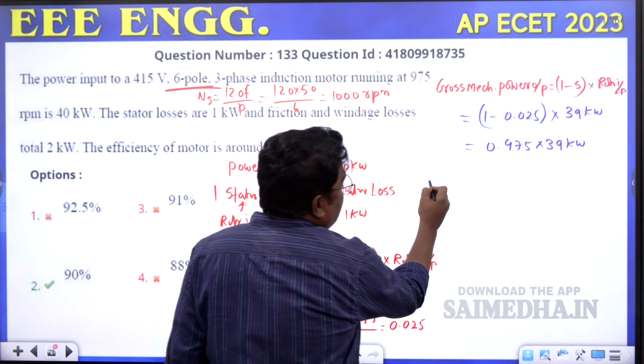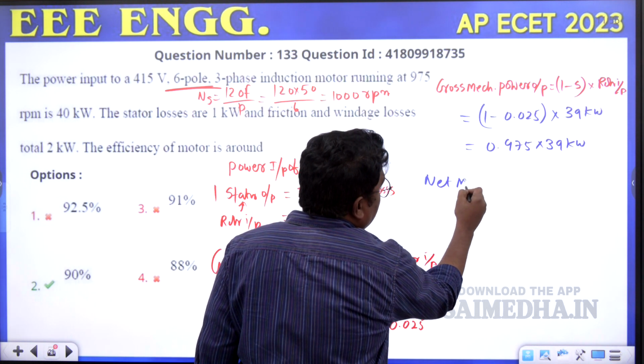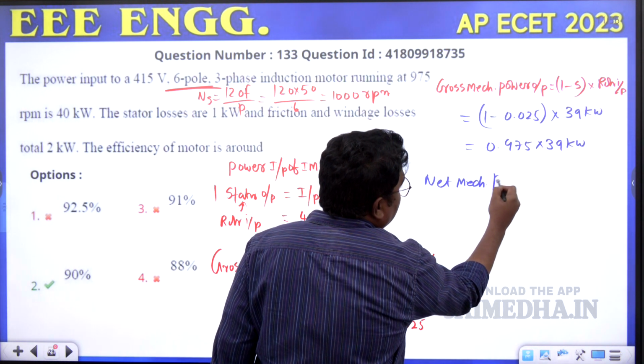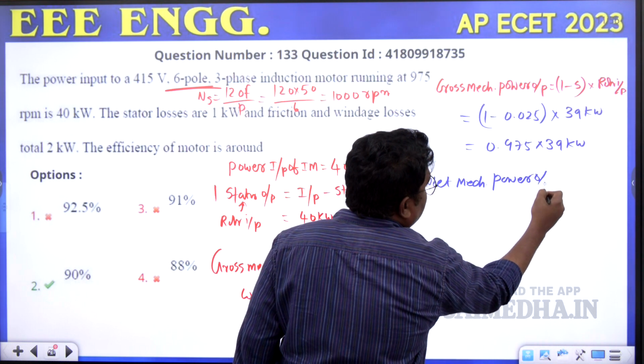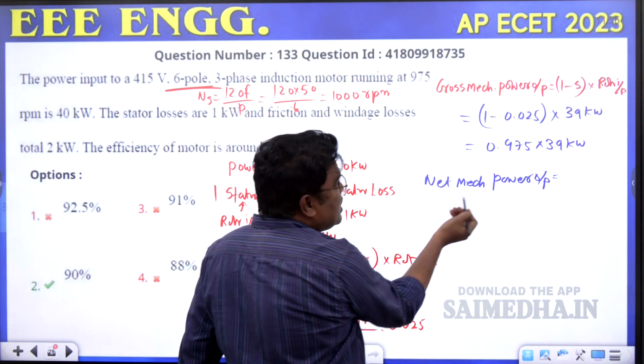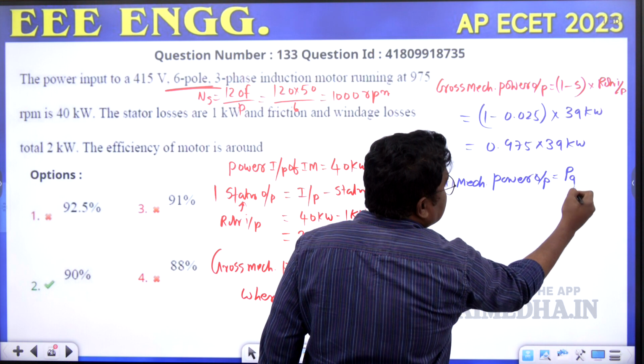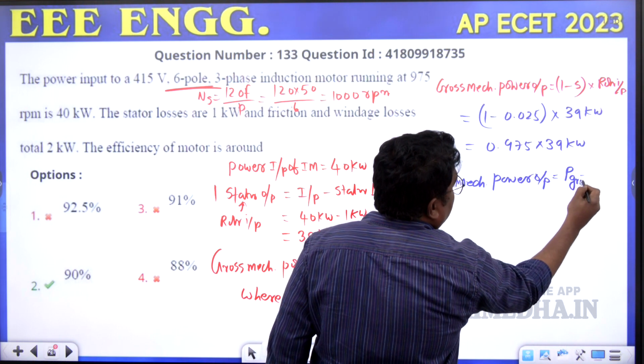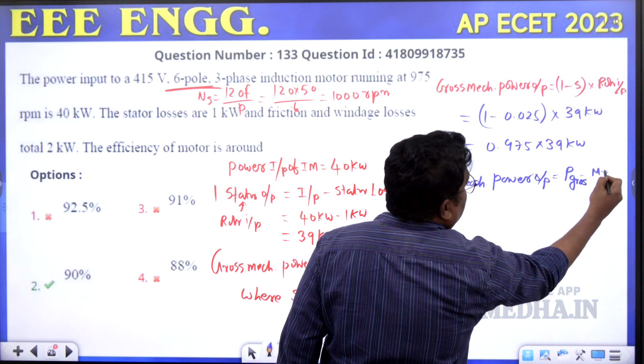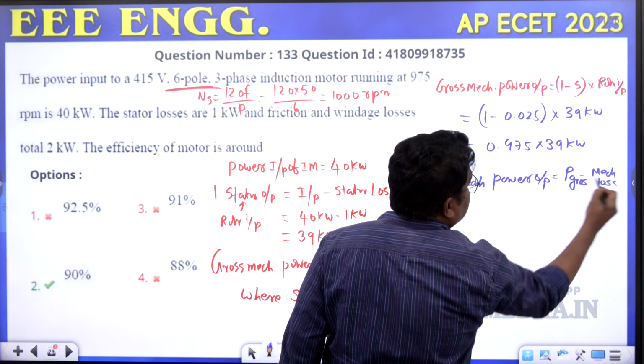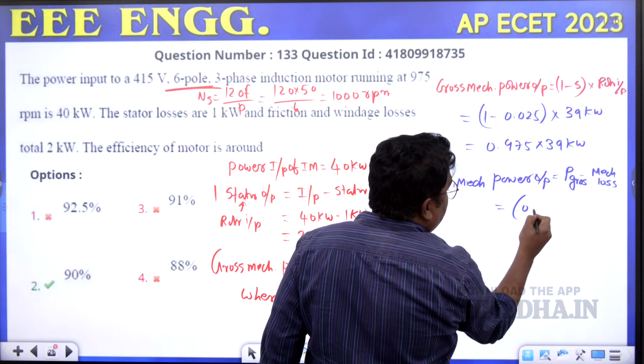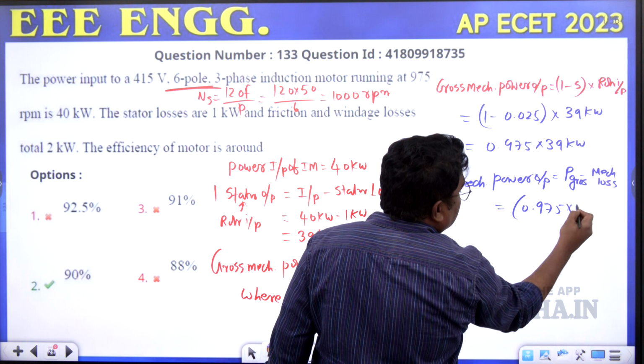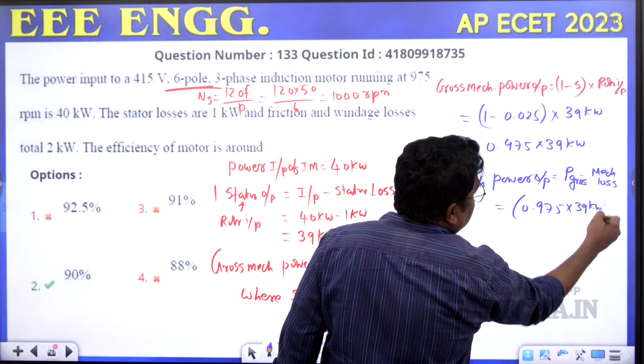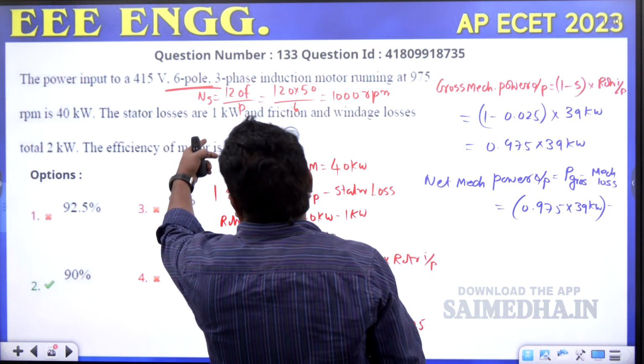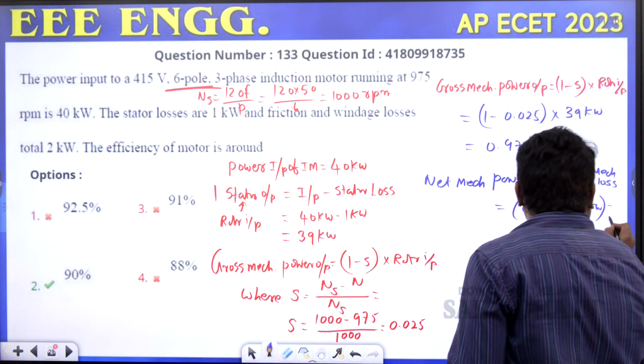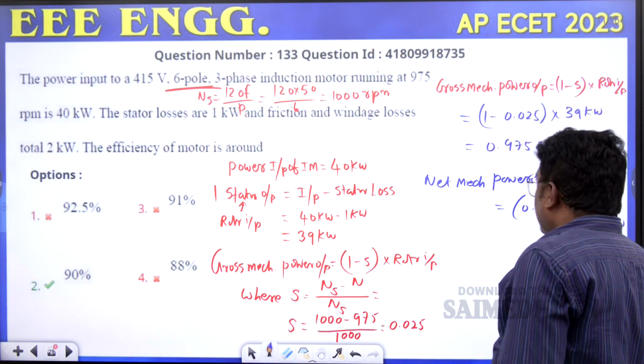Now we require the net mechanical power output. How do we get the net mechanical power output of the machine? It is equal to the gross mechanical power output, Pg, minus the mechanical losses. So it is equal to 0.975 into 39 kilowatts minus the mechanical losses, which are 2 kilowatts.